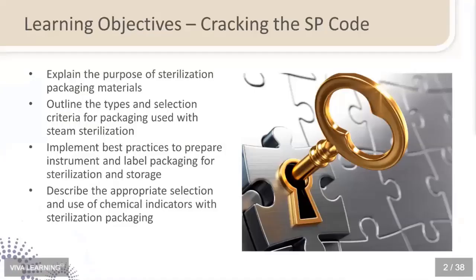And so when we talk about cracking the code of sterilization packaging, it actually begins with understanding the method of sterilization that we're using. And in dentistry, we tend to use saturated steam primarily. However, we have to make sure that if in our practices we are using dry heat or unsaturated chemical vapor, that we're also choosing sterilization packaging that's compatible with that method of sterilization. We also have to look at the type and the design of the material that we're using, the specific design and type of the instruments that we're going to be sterilizing, and then select the best material and or wrap that's going to be able to secure the contents during sterilization, and then also maintain sterility during delivery and storage for use with patients.